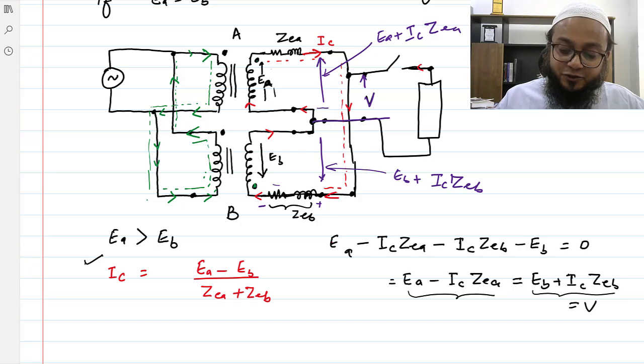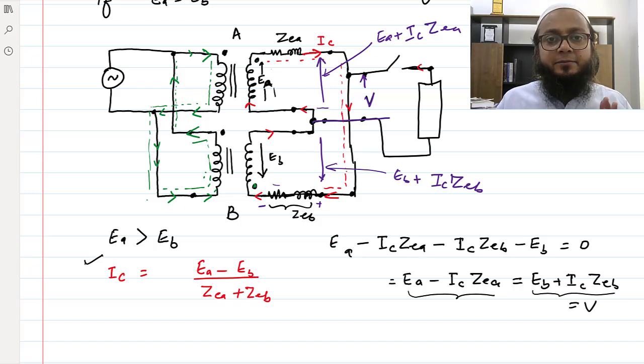So we should have equal turn ratio, and the transformer should be properly connected with correct polarity using the dot convention. First, because if polarities are not checked and you connect it directly, there are chances you will short a huge potential with a zero resistance path, causing a huge circulating current that will damage the transformer. And if there is a difference in the voltage ratio, there would be an equivalent circulating current flowing in both the primary and secondary, even without any load connected. So these two conditions we have discussed.